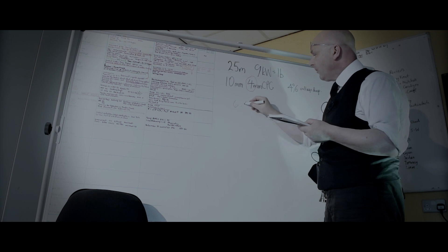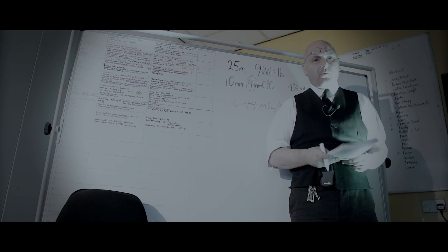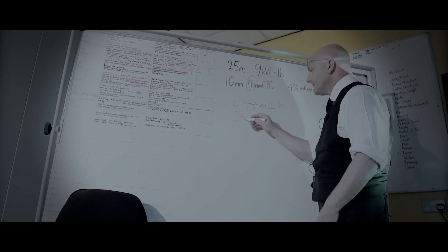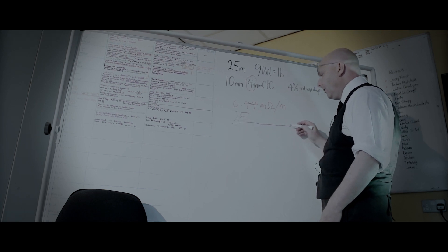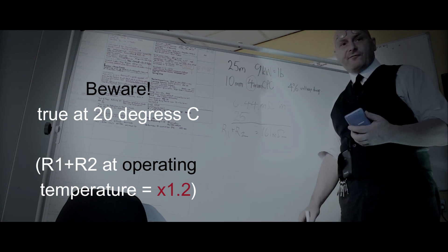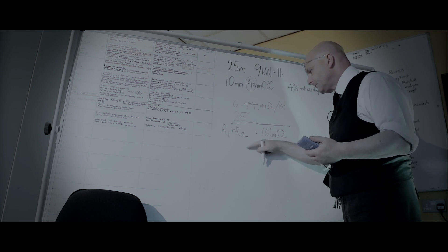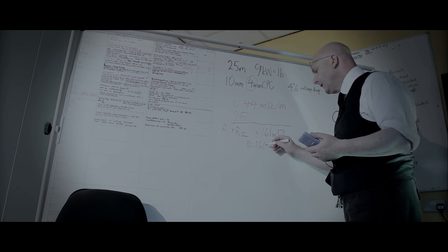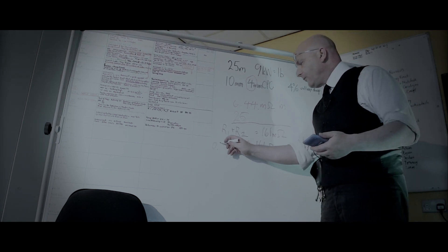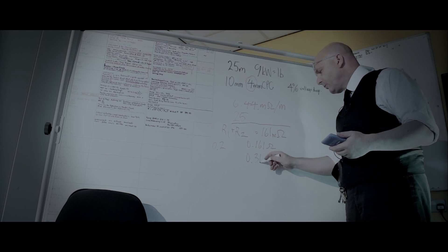It's 6.44 milliohms per meter. We can now work out, by multiplying it by 25, the total resistance of R1 plus R2. So we've got a very low resistance in that system: 0.161 ohms. We add our Ze to that — let's give ourselves a Ze of 0.2 — that's 0.361 ohms.